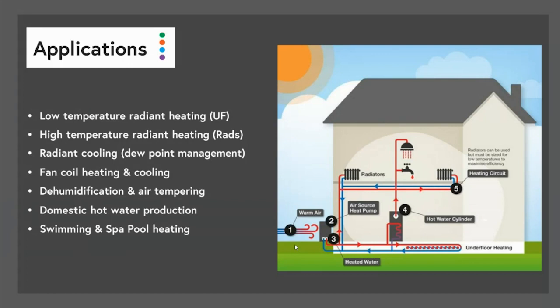Which can also be used in cooling mode. So we can do radiant cooling with underfloor and also with panels in the walls and ceilings using dew point management. That's something we'll talk about in a little bit, which is to do with controls. That's to do with eliminating the possibility of condensation on surfaces because the temperature of the surface has been dropped too low. We can also run fan coils in heating and cooling mode.